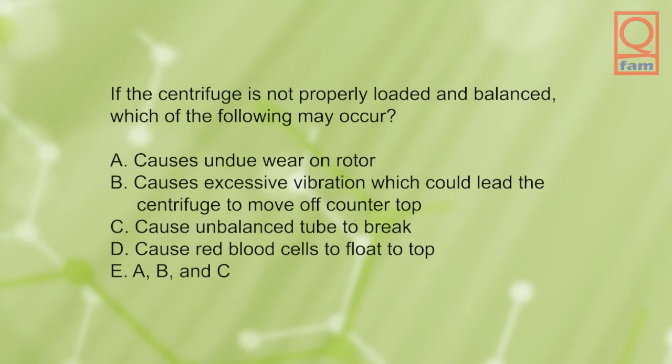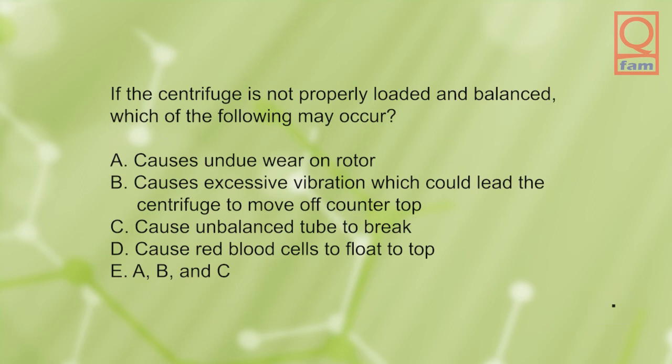If the centrifuge is not properly loaded and balanced, which of the following may occur? A) causes undue wear on rotor, B) causes excessive vibration which could lead the centrifuge to move off countertop, C) cause unbalanced tube to break, D) cause red blood cells to float to top, E) A, B and C. The answer is E, A, B and C.